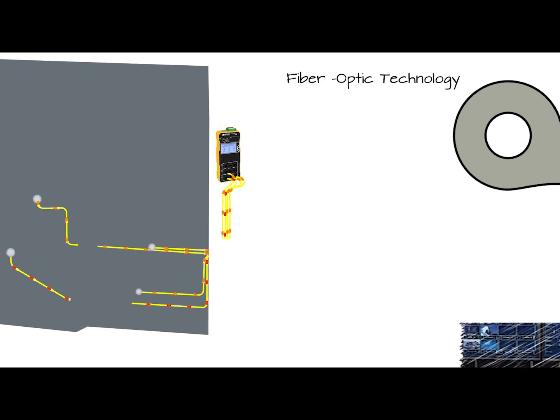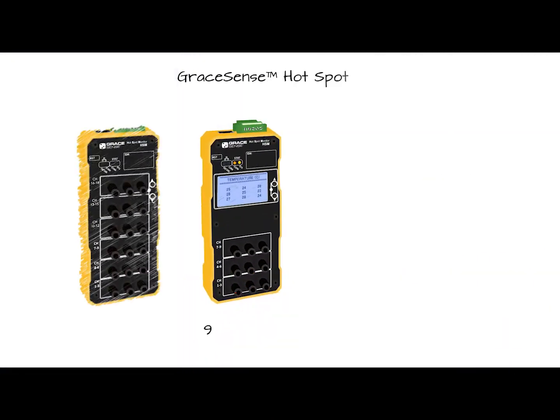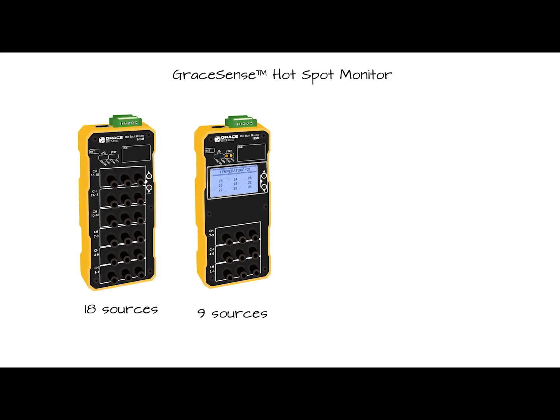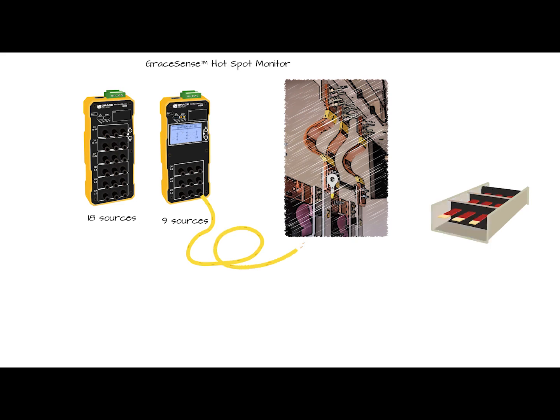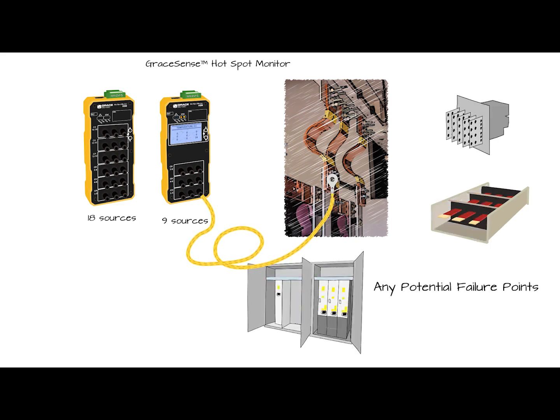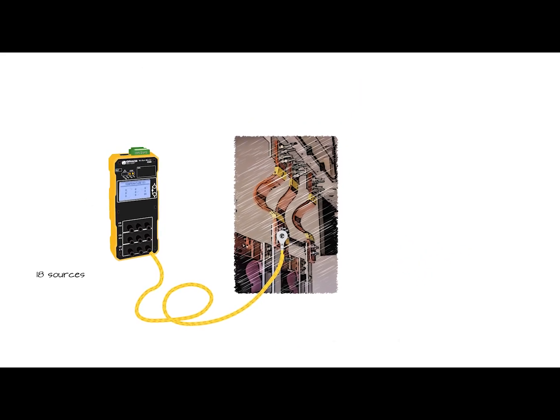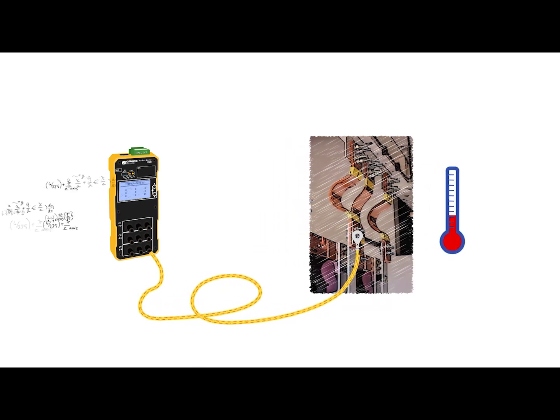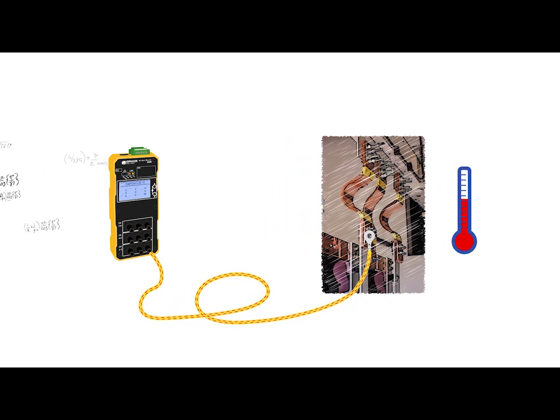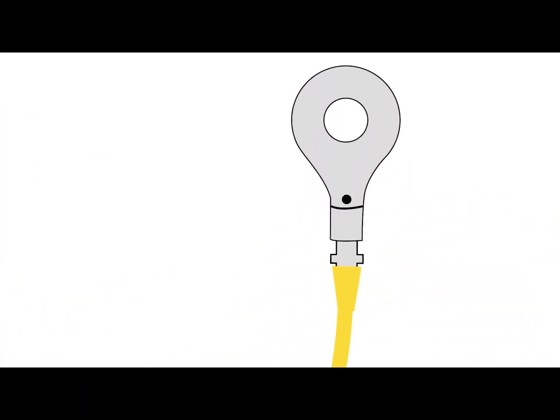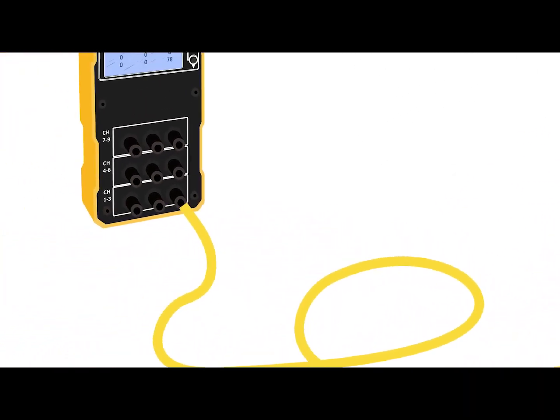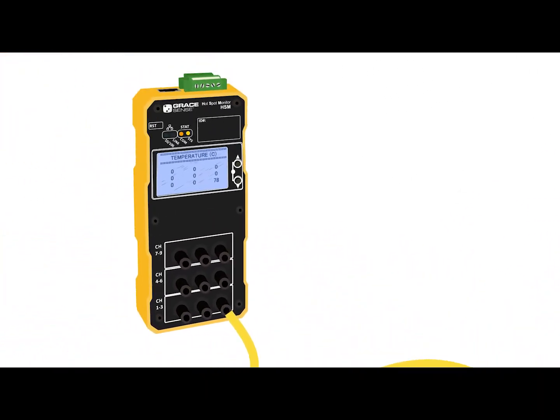The HSM utilizes patented fiber optic technology, providing constant temperature data available in 9 or 18 independent sources. The fiber probes can be mounted onto electrical bus bars, bus ducts, transformers, or any other source of heat. The Hotspot Monitor provides a unique combination of patented fiber technology and advanced algorithms that convert the change in light intensity to temperature. The patented fiber probes securely connect to a ring-style connector that conveniently mounts to the source of heat, while the other end connects to the HSM module.